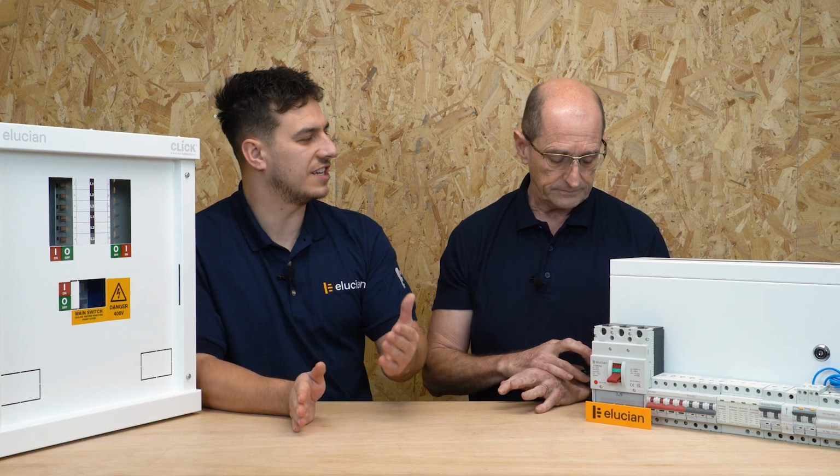Type D takes that further. In essence, you're not dealing with small scale motors, you're not dealing with controlled lighting circuits and the like. You're dealing with big grunty things like welding kits and heavier motors with very large induction spikes that might cause a type C device to operate even though there's no fault, but that would be appropriate at that level. Okay, so how do we know when to select the right one then, Tim?